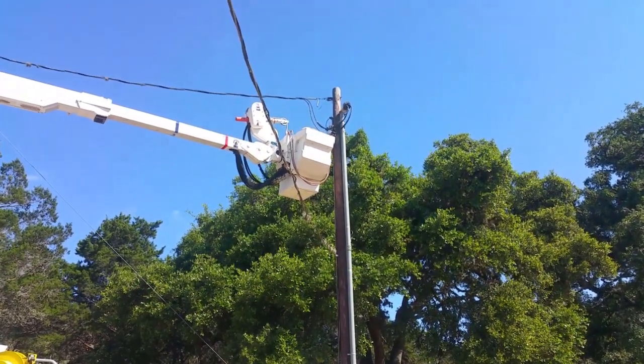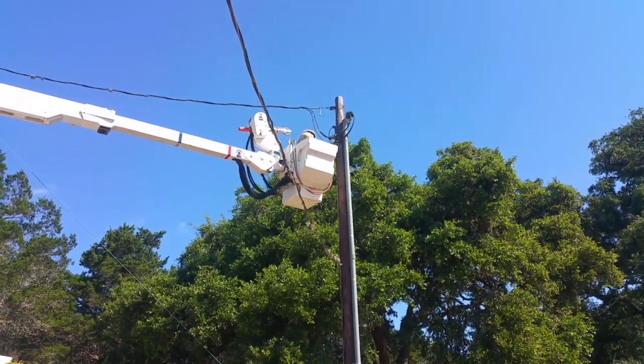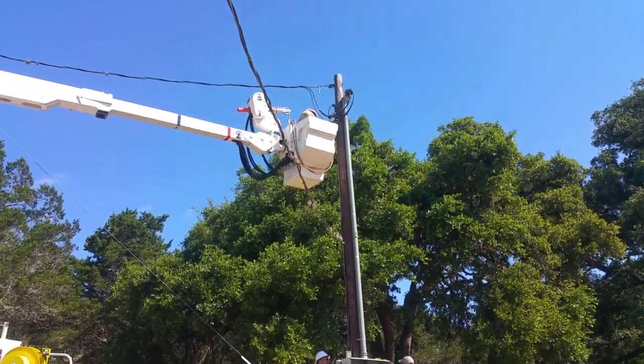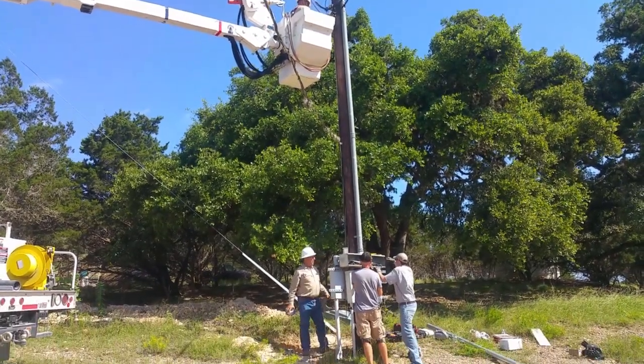There's a hole in the pipe up there in that conduit up by the service coming in. I'm going to pull that and repair it since it's 400 amps coming in. So that galvanized pipe going up — that pole there is going to be replaced.